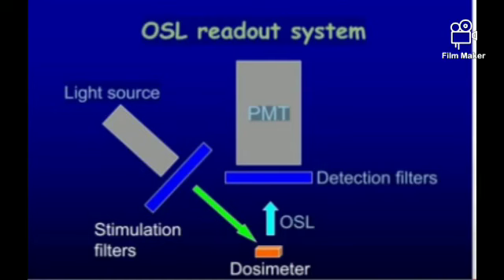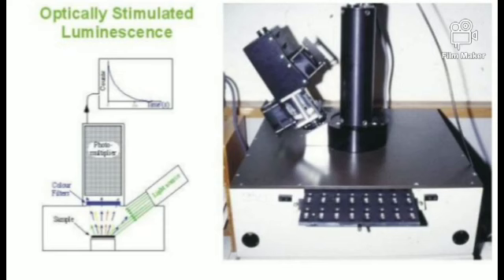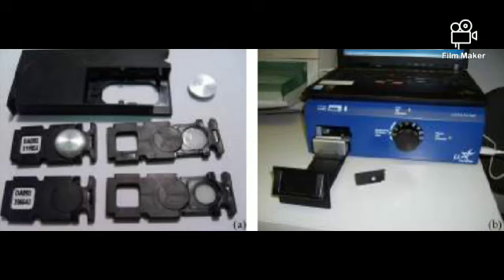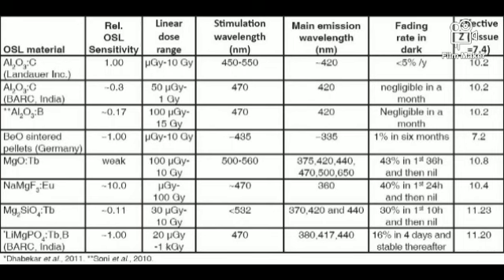You can see here the OSLD reader system. The small chips or sticks are placed into the reader. A laser light excites the material from the ground state to an excited state, emitting a small blue-colored light. This light passes through a light detection filter and into a PMT — photomultiplier tube — which then produces the report in digital format on the computer.